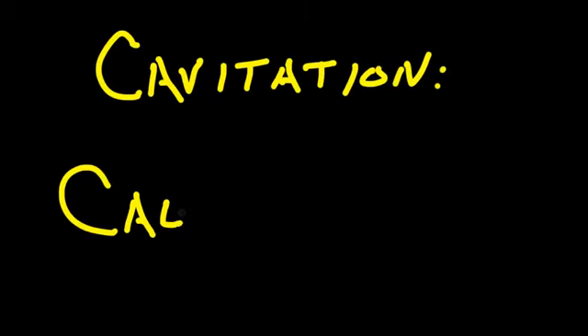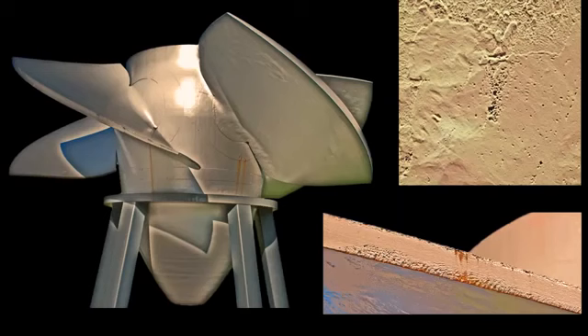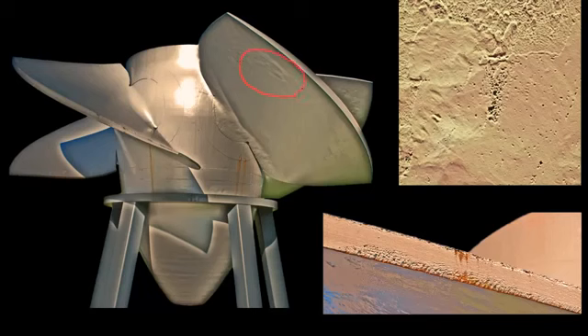In this video, I will describe some of the causes and effects of cavitation failure. These pictures show examples of the type of damage that is caused by cavitation. This is a picture of a large Kaplan-style turbine runner that is now removed from service at a hydroelectric power generation facility. On the low pressure side of the turbine blade, we can see some evidence of the type of surface pitting that is typical of cavitation damage.